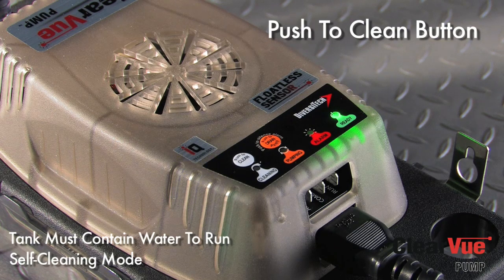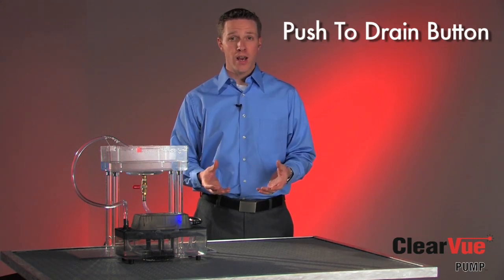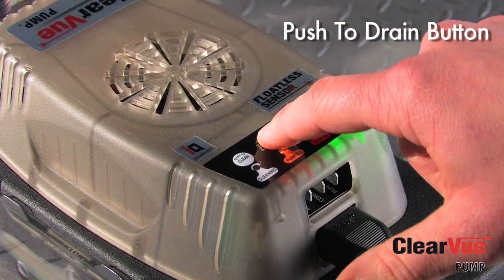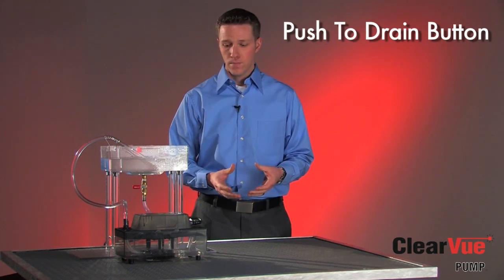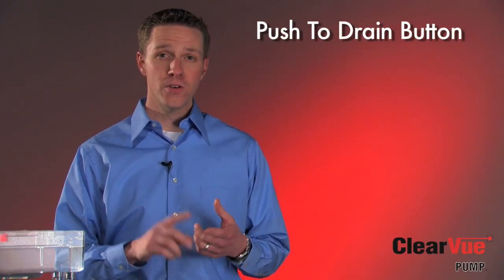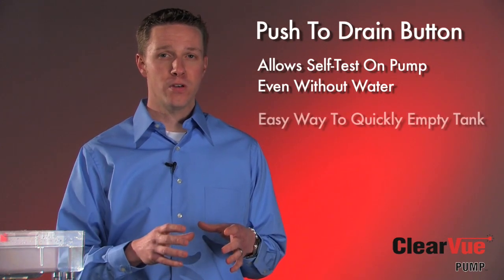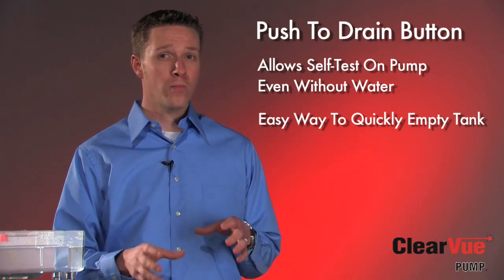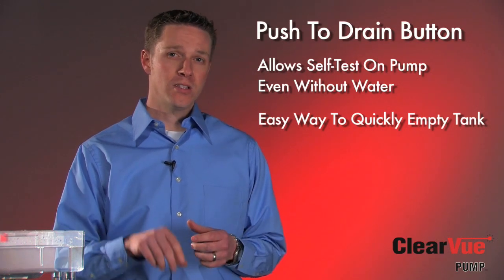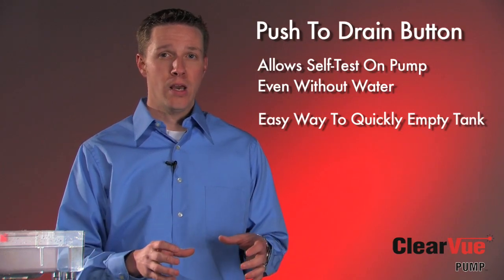ClearVue also has a push-to-clean button that will start a self-cleaning cycle anytime you want, so you can run a clean cycle just like I showed you before. The other feature I want to show you is our push-to-drain button. When there's water in the tank, you can simply push the drain button and ClearVue will quickly remove the water from the tank — just like that. With the push-to-drain button, there are two key features. The first is that the contractor can actually test the pump without having to pour any water into the tank. The second is that if there's been any cleaning to the air conditioning system or the pump itself with chemical solution in the tank, you can simply push that drain button and it will pump all that solution out without having to reach in to activate a float or shake the tank.